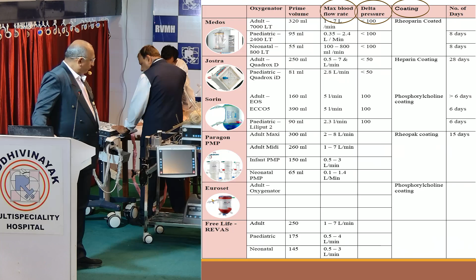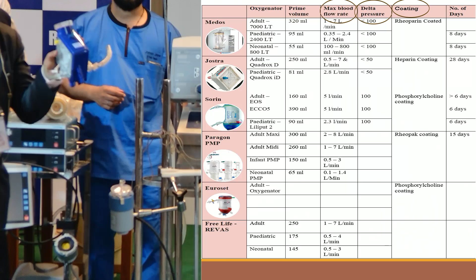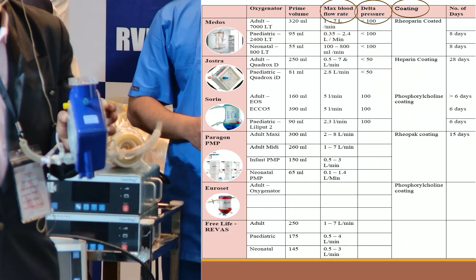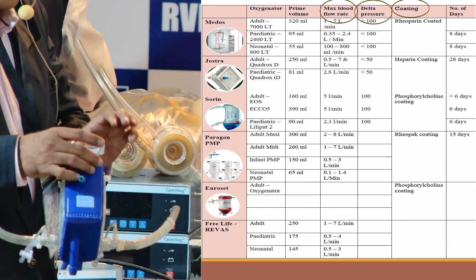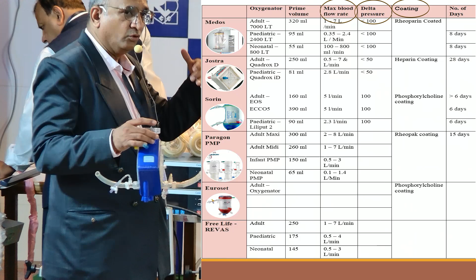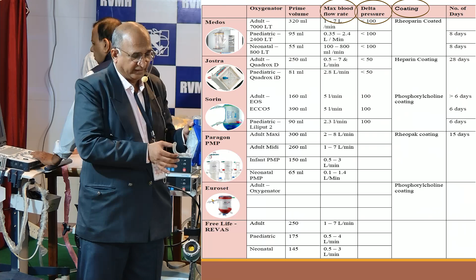See, the oxygenator is an independent body. It is connected to the circuit with the help of only tubes. So you can use any oxygenator with any of the circuits. It is not type specific. So in a Maquet machine I can use a Quadrox oxygenator, I can use a Sorin oxygenator, I can use a Medos oxygenator, a Euroset oxygenator, I can use any oxygenator because it is not attached to the machine, it is attached with the help of tubes only. So I can use any of the oxygenators with any of the machines.